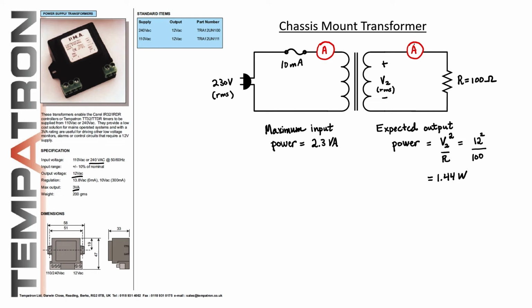I'm going to measure the current passing through the primary side and the secondary side simultaneously. Efficiency is defined as power out divided by power in. If the transformer were perfect, these powers should be identical, but we know that's not going to be the case. Output power will be I2 squared times R, and I2 will be directly measured.